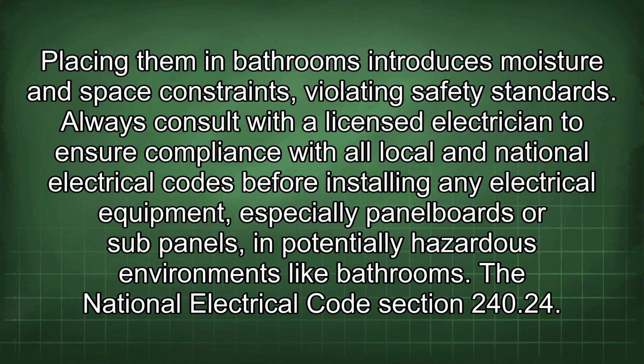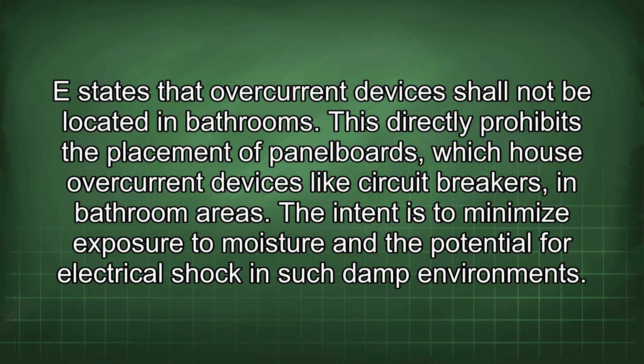The National Electrical Code Section 240.24(E) states that overcurrent devices shall not be located in bathrooms. This directly prohibits the placement of panel boards, which house overcurrent devices like circuit breakers, in bathroom areas. The intent is to minimize exposure to moisture and the potential for electrical shock in such damp environments.